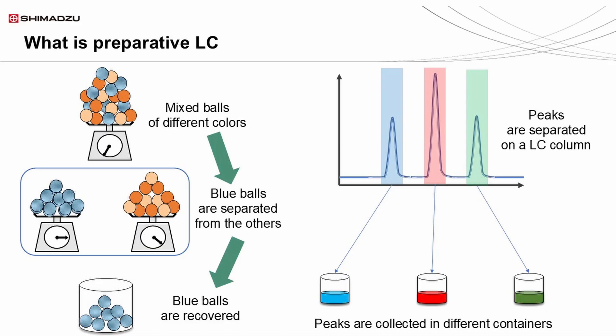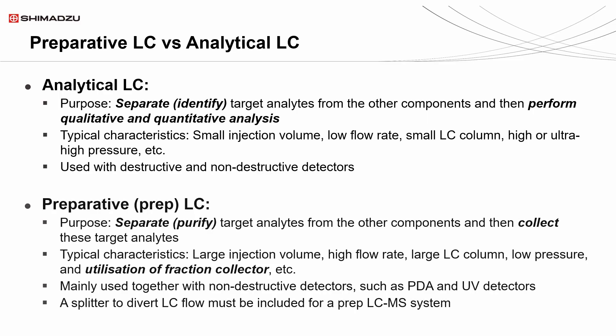Preparative HPLC is a technique used to separate and collect target compounds from a mixture at a larger scale, as shown here with the separation of blue, red, and green fractions. Analytical and Preparative Liquid Chromatography serve different purposes. Analytical LC focuses on separating and identifying analytes for qualitative and quantitative analysis, using small injection volumes, low flow rates, and high pressure columns. In contrast, Preparative LC is designed for purification and collection of target analytes, employing larger injection volumes, higher flow rates, and fraction collectors.